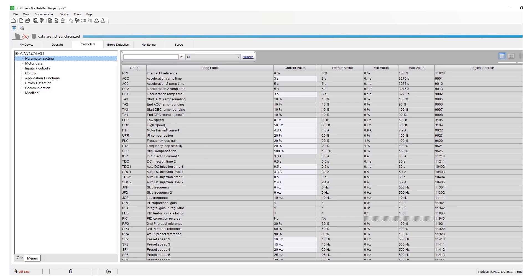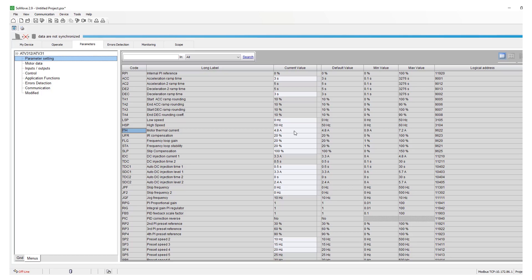ITH is motor thermal current. The thermal current must again match the motor FLA, so make sure that is set correctly.